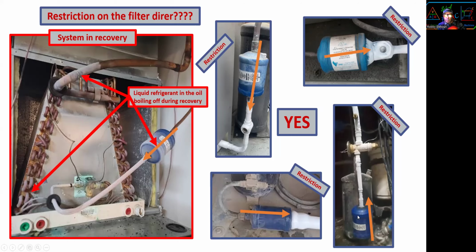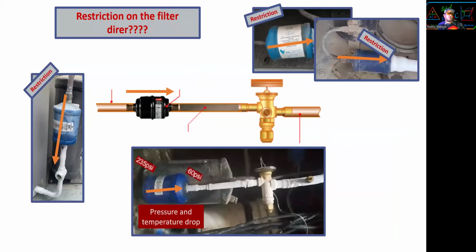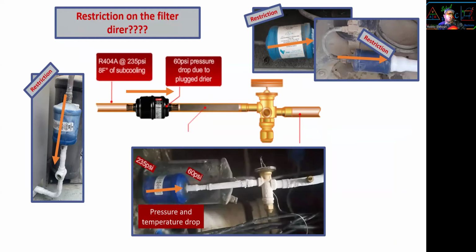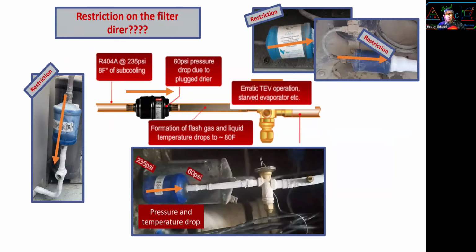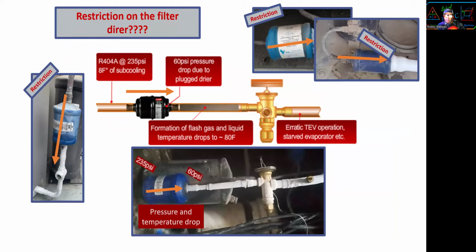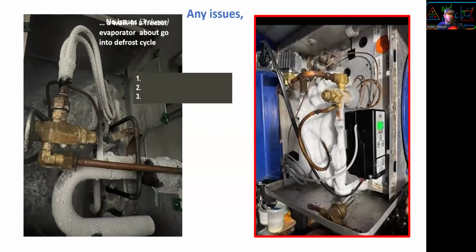These are restrictions because you can see ice after the filter dryer, which we're not supposed to see ice on the filter dryer. All right, restriction on the filter dryer. The pressure will drop. We cannot measure the pressure, but we can know by temperature change. Okay. And so many times people tell me it's a bad TXV, but it's actually a bad filter dryer. All right, now, any issues? This one, no issues. There's 3 clues. The one on the red has issues.